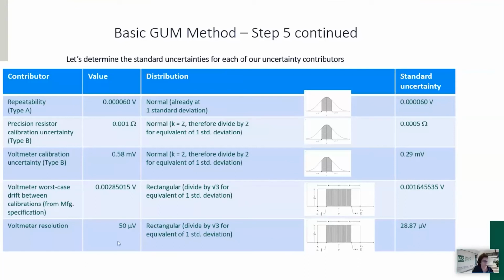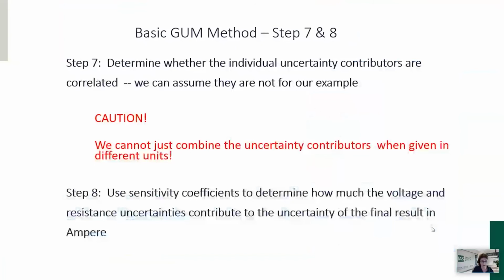Then we have the voltmeter resolution. We already divided by 2 to get that half value, 50 microvolt. And again, we have no idea whether it could be anywhere between these limits, so we assume a rectangular distribution and divide by the square root of 3 to get to our standard deviation, the equivalent of which is our standard uncertainty.